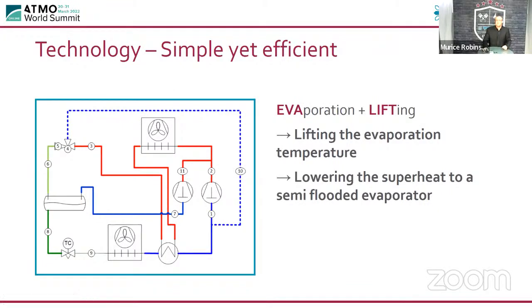evaporation and lifting. So lifting the evaporation temperature and then lowering the superheat to a semi-flooded evaporator. What that does is we move the superheat away from the evaporator, and then we control the superheat at the pack with a plate heat exchanger that's specially designed. As we know, the superheat on a standard system ranges between, I don't know, 6 and 10 K.